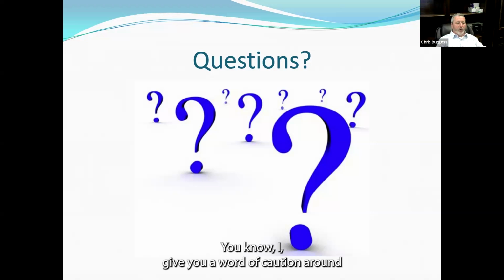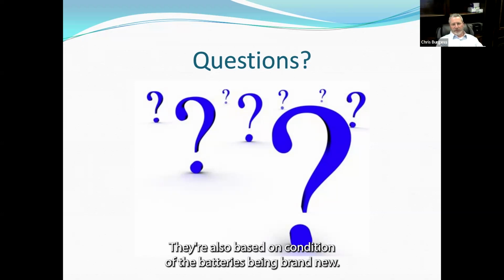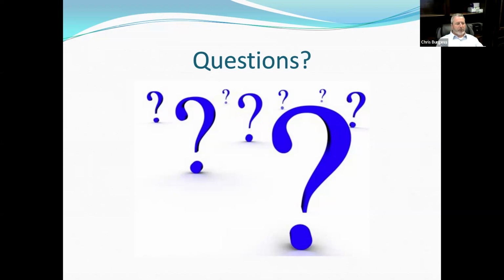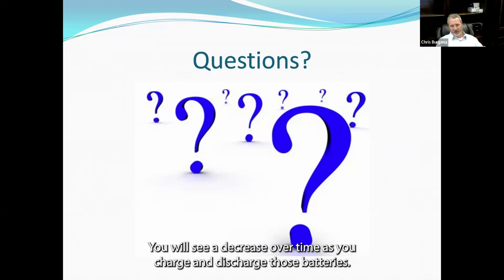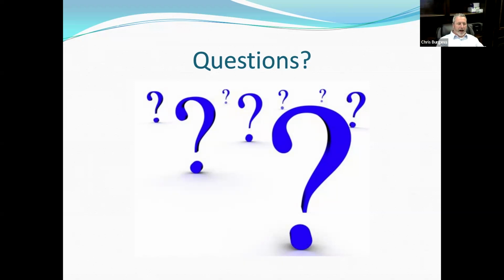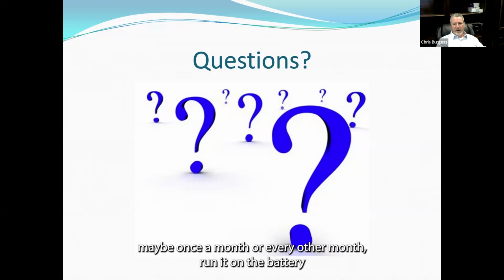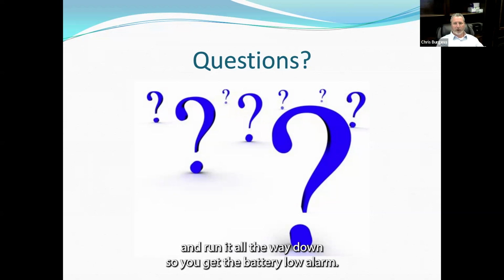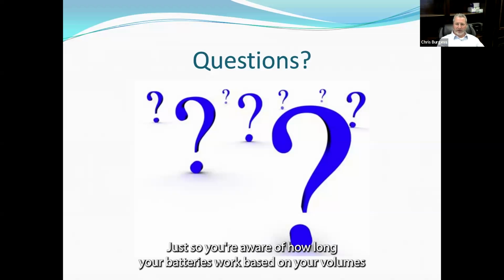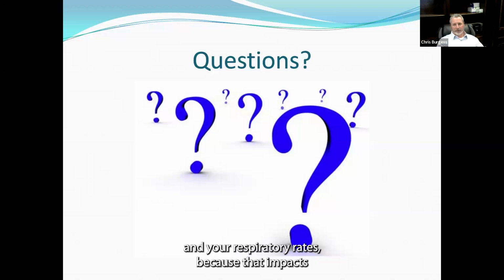I give you a word of caution around any battery statements from any manufacturer. They publish their battery life based on just standard settings on a test lung that doesn't change respiratory rate. They're also based on the batteries being brand new. You will see a decrease over time as you charge and discharge those batteries. I always recommend that people run their device maybe once a month or every other month on the battery, and run it all the way down till you get the battery low alarm, just so you're aware of how long your batteries work based on your volumes and your respiratory rates, because that impacts the duration of the batteries a lot.